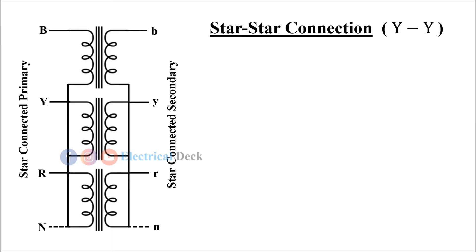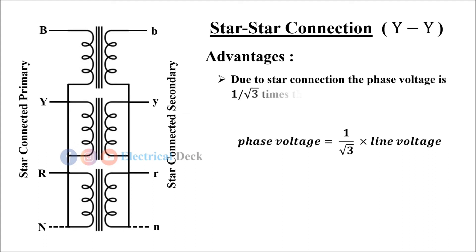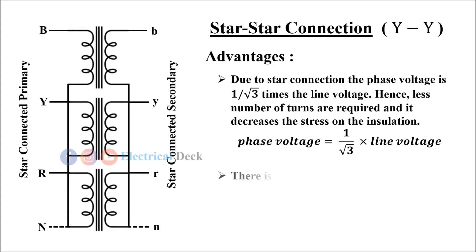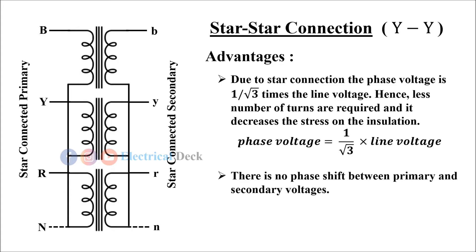The advantages of using star-to-star connection are: due to star connection, the phase voltage is one by root three times the line voltage, hence less number of turns are required and it decreases the stress on the insulation. There is no phase shift between primary and secondary voltages. As neutral is available, it is well suited for a three-phase four-wire system.